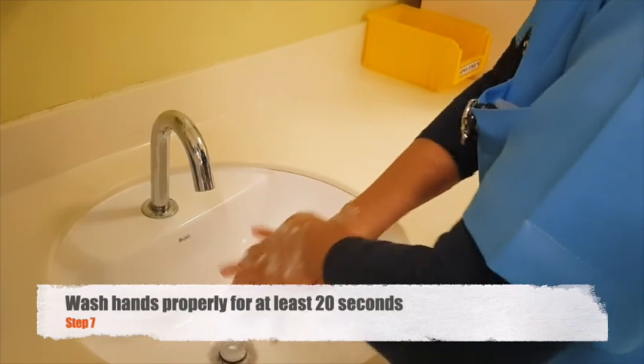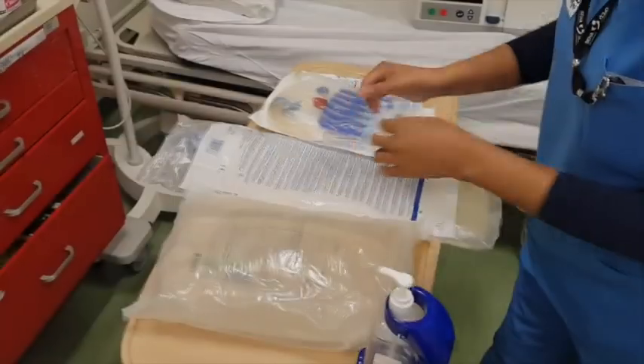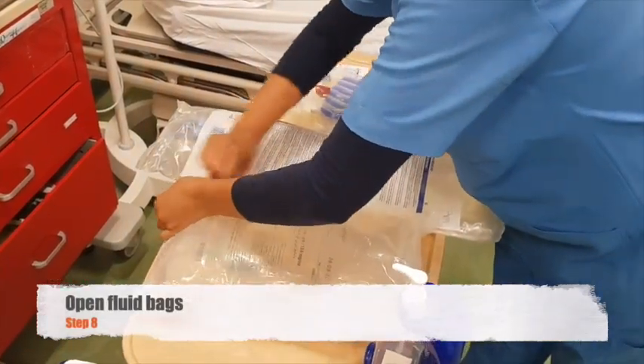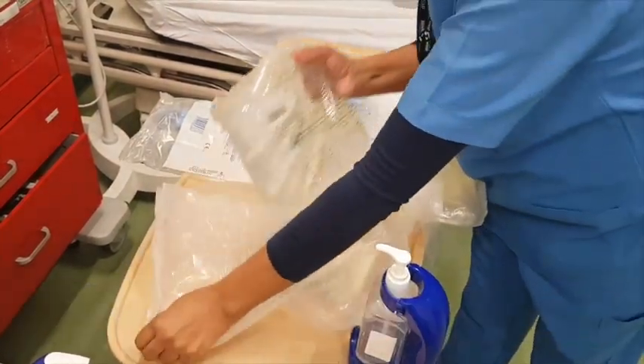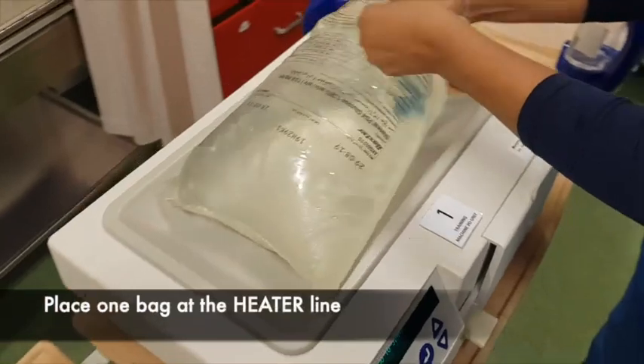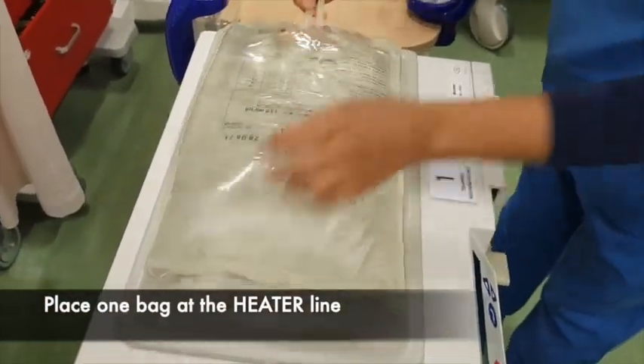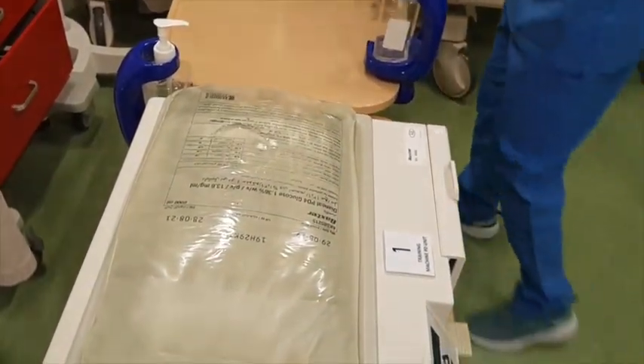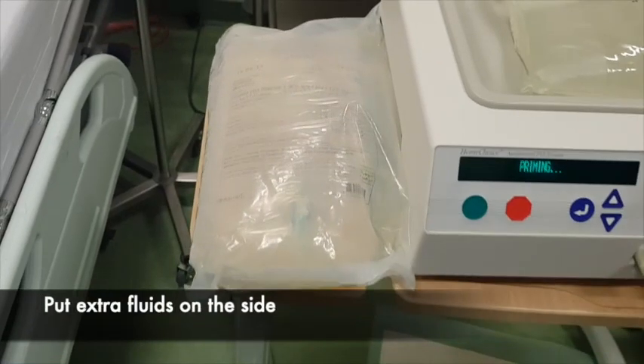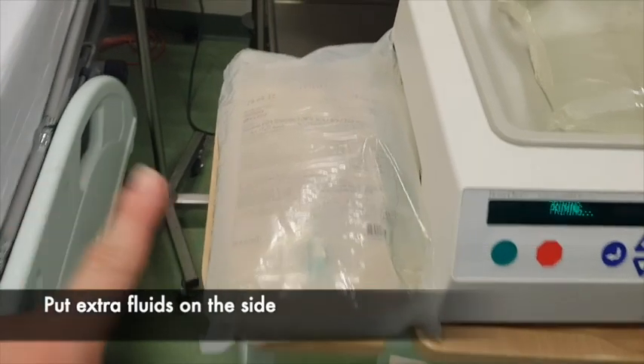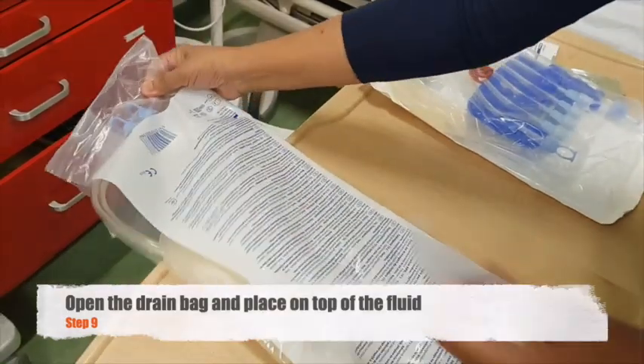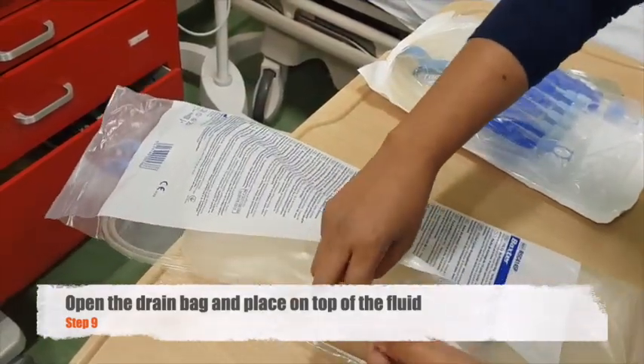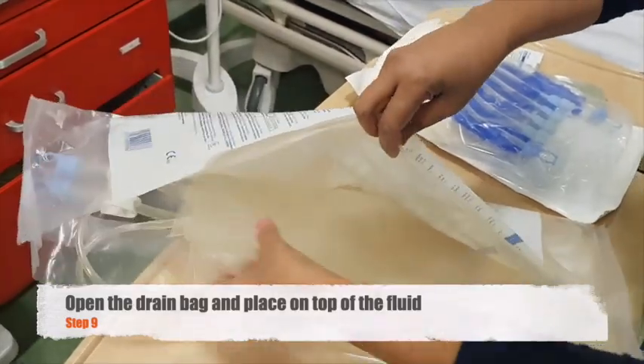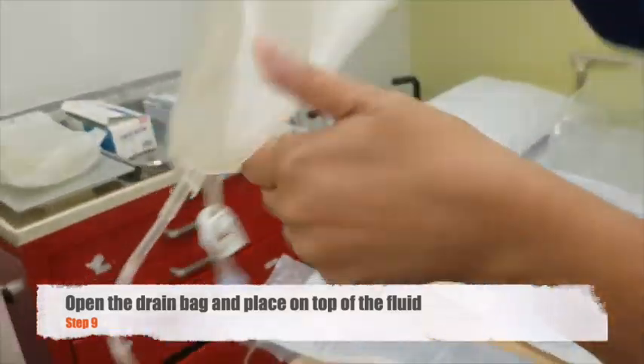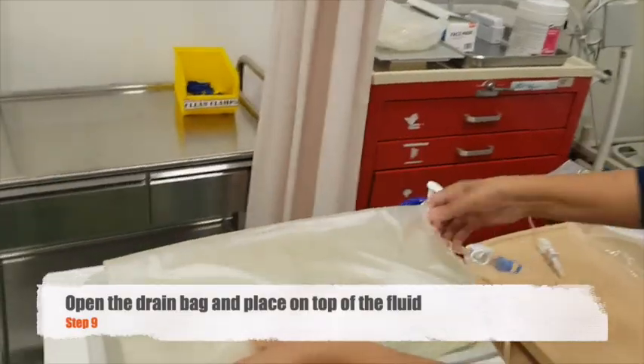Wash your hands again properly for at least 20 seconds. You can now proceed to open the PD fluid bags. Place one of the bags on top of the heater line. In case your treatment requires more than one PD fluid, put the extra fluids on the sides of the table. You may now proceed to open the drain bag. The package usually includes 2 drain bags, but in this instance, we will only be using one. Take the bag and place it on top of the fluid on the machine.